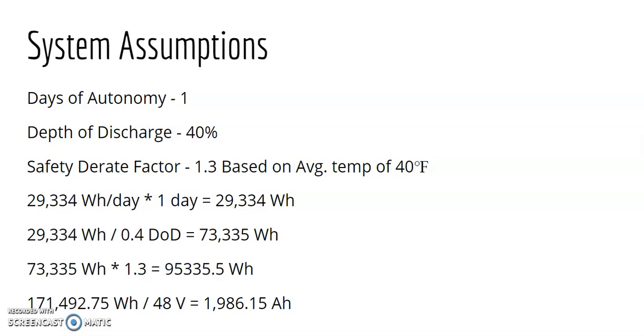So we needed to make some assumptions. And these are the days of autonomy, the depth of discharge, and the safety derate factor. And so we have 1 day of autonomy, where the system can provide 1 day worth of electricity in the case of another blackout, and a 40% depth of discharge to help extend the life of the battery, as you never want to drain the battery all the way. And for the safety derate factor, we found that the average low temperature in Houston, Texas is 40 degrees, and from the safety derate factor chart, that temperature equated to 1.3 of the safety factor.